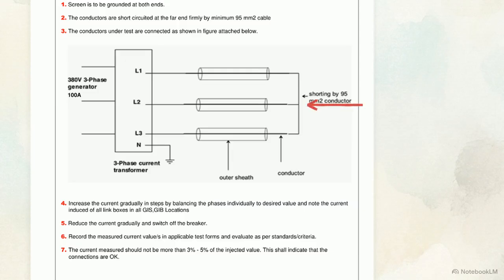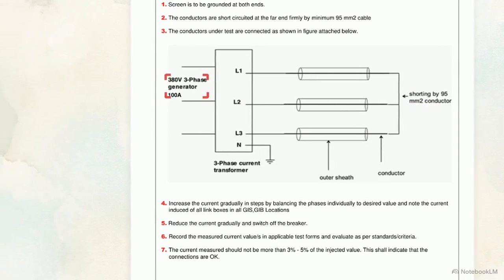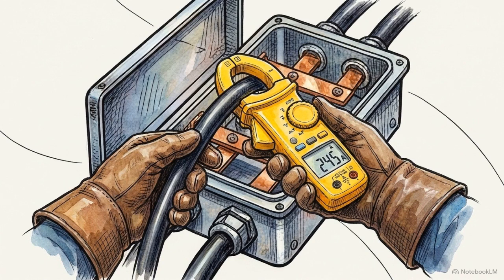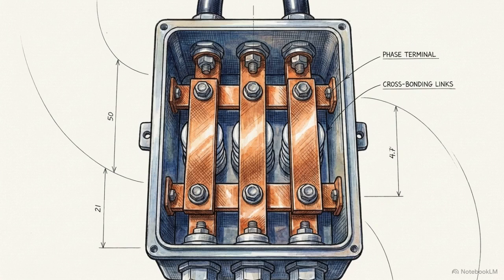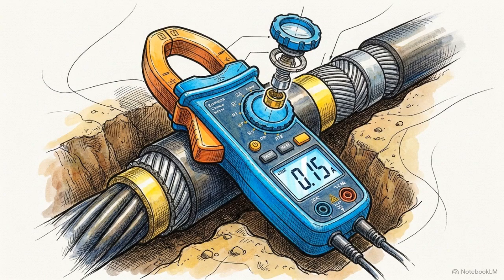Cable screens are grounded at both ends, far-end conductors are short-circuited, and a 380-volt three-phase generator injects balanced current into the conductors under test. Technicians utilize a calibrated clamp meter to measure the induced current at every specific link box and relevant GIS or GIB location. The measured current must not exceed 3 to 5% of the injected value. Proving that the induced current remains suppressed validates that the sheath cross-bonding links are installed correctly. Precise cross-bonding neutralizes dangerous electromagnetic interference, permitting stable parallel operation.